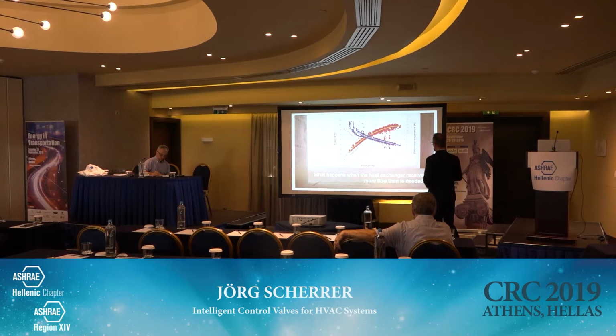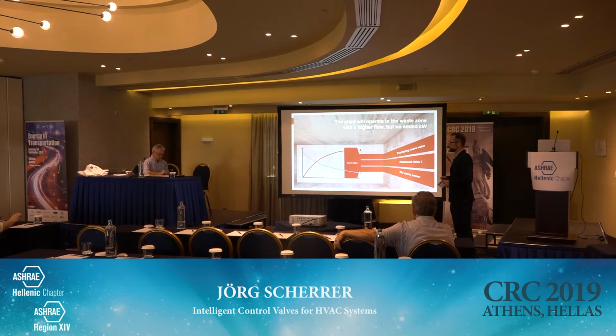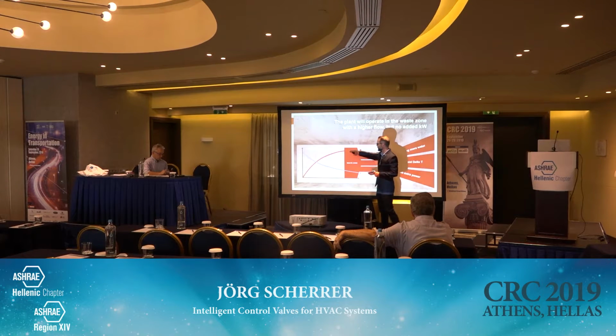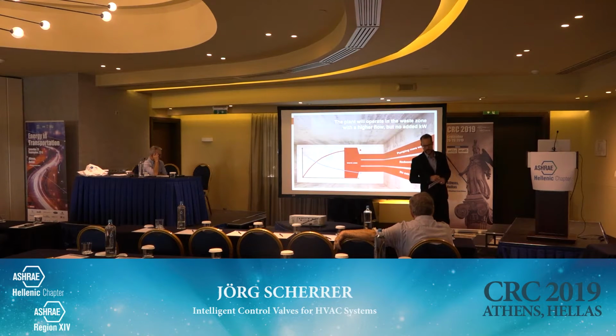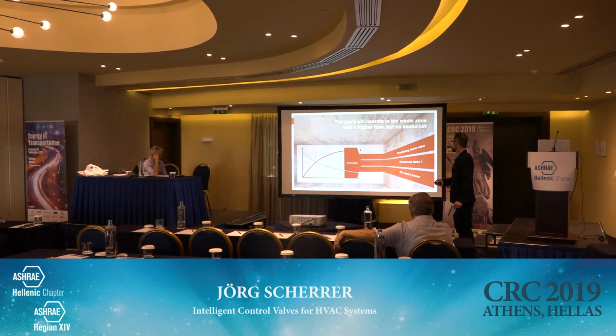Now, at a certain point, this curve will be flat. Typical behavior of a heat exchanger is that when the curve is flat, I pump more water around in the system without gaining more power output. In this waste zone, the power output curve is flat. So I have too much water pumping around the circuit, and when I pump too much water around, I have a very small delta T, inefficient use of energy, higher operating costs on the pump side, and no extra power on the heat exchanger. This is what we try to avoid with modern control valves.